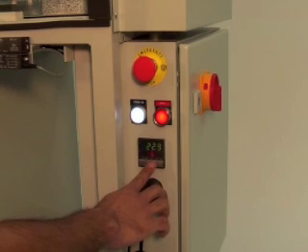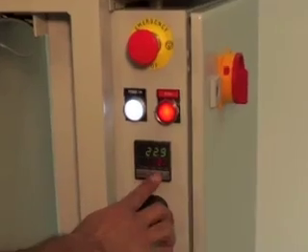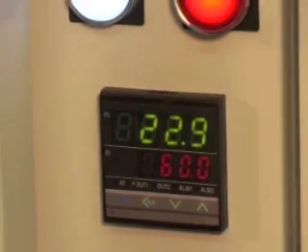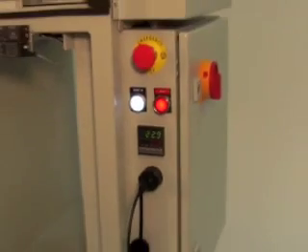Key features include automated pre-programmable sample conditioning and a PID controlled temperature cabinet with fully glazed doors to maintain the specimen temperature throughout the test at ±1 degree centigrade.